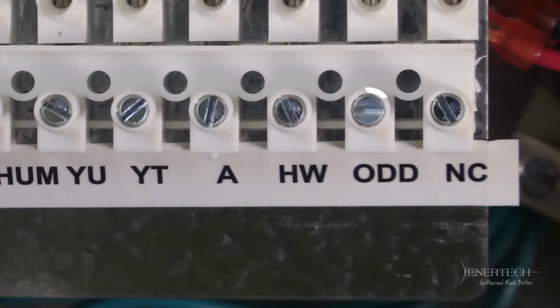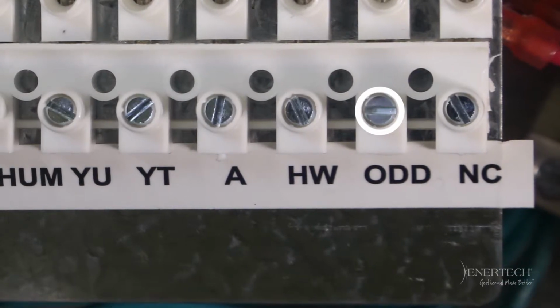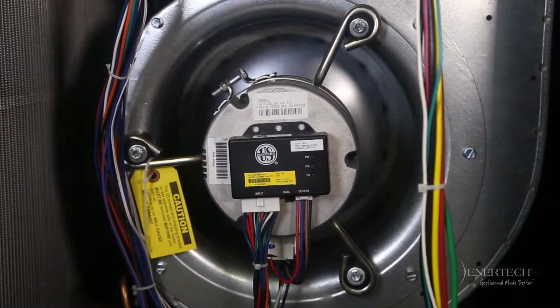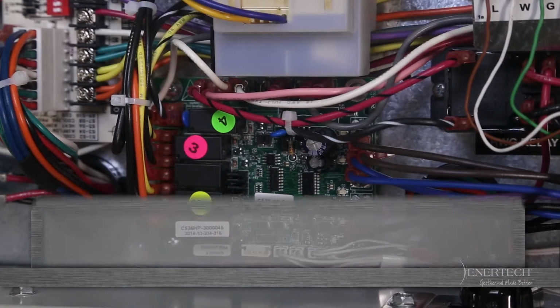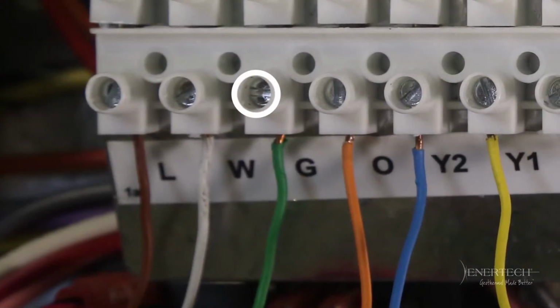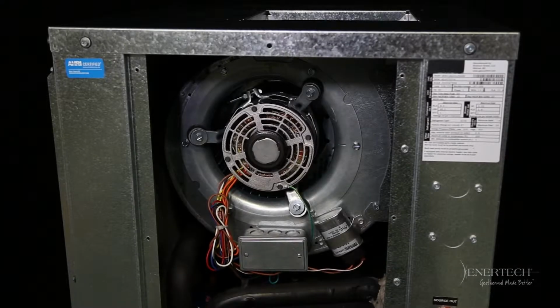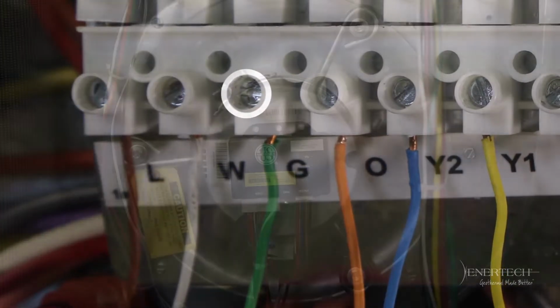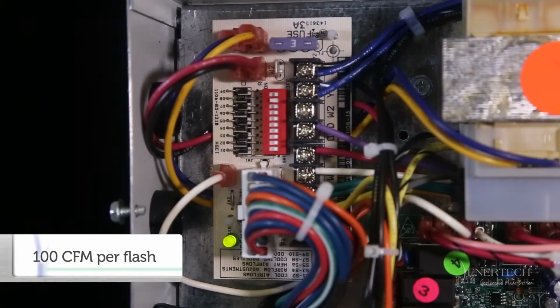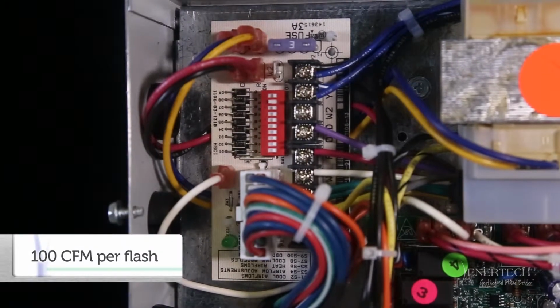A field connection is provided at the terminal strip for external control of the on-demand dehumidification (ODD) feature for the variable speed ECM fan motor, which automatically lowers the fan speed when the space humidity is higher than the set point. Either connection may be used with a thermostat that includes humidifier or dehumidification outputs. In ECM-equipped models without an accessory terminal strip provided, connect ODD and G on the ECM board directly, packaged units only. For units equipped with PSC blower motors, connect the thermostat's humidifier terminal to G on the unit's thermostat terminal strip. On units equipped with an ECM blower, an LED on the ECM fan control board flashes one time per 100 CFM when the unit's fan is operating to indicate airflow.